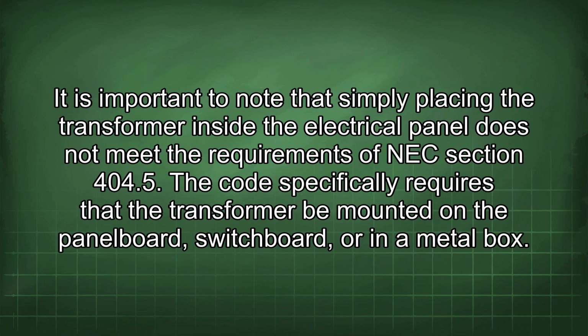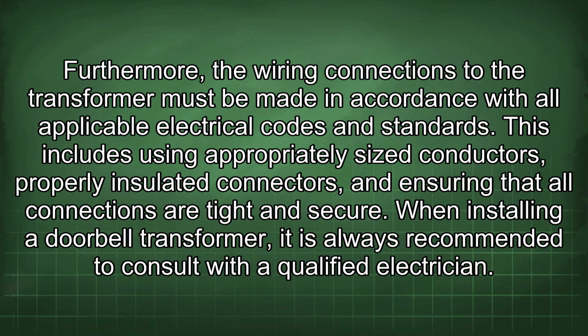It is important to note that simply placing the transformer inside the electrical panel does not meet the requirements of NEC Section 404.5. The code specifically requires that the transformer be mounted on the panel board, switchboard, or in a metal box. Furthermore, the wiring connections to the transformer must be made in accordance with all applicable electrical codes and standards. This includes using appropriately sized conductors, properly insulated connectors, and ensuring that all connections are tight and secure.